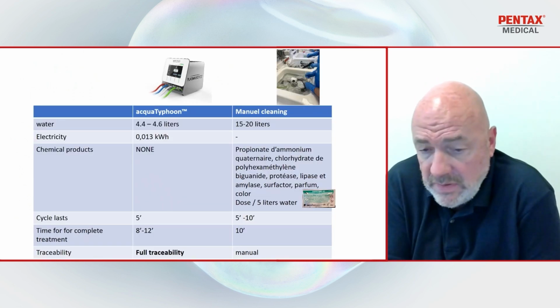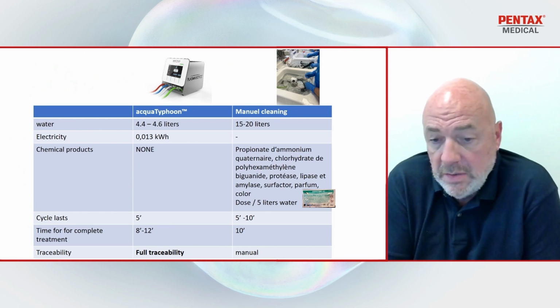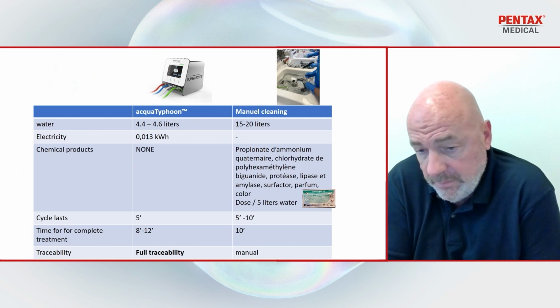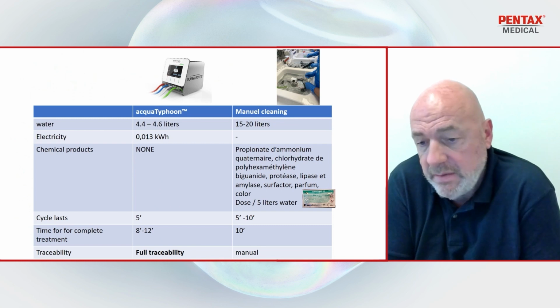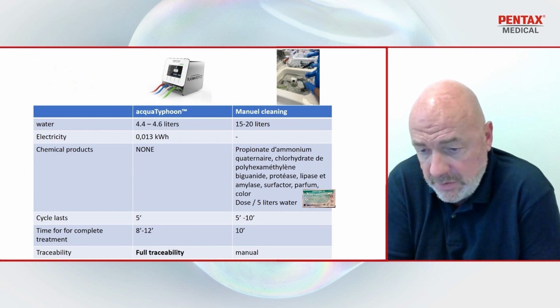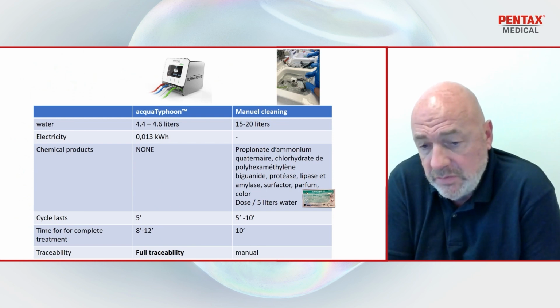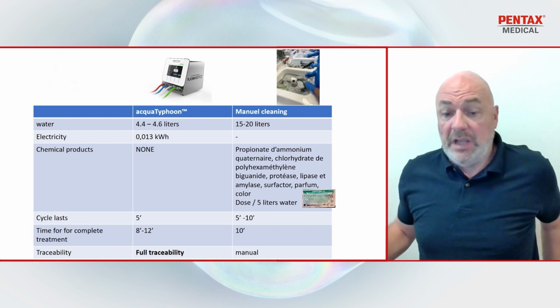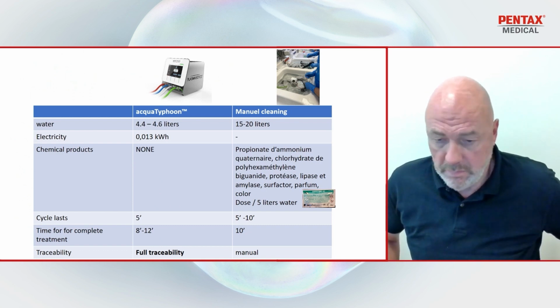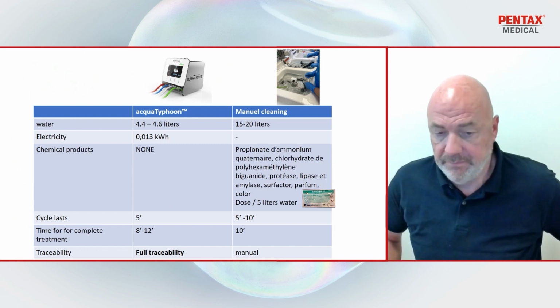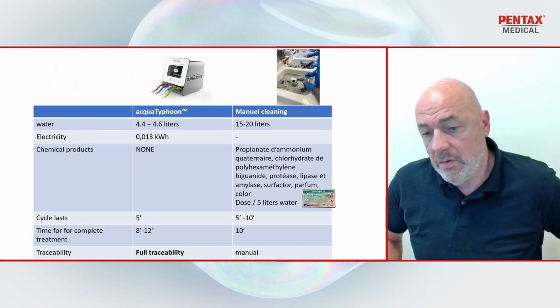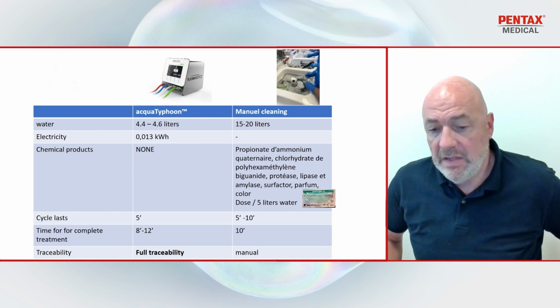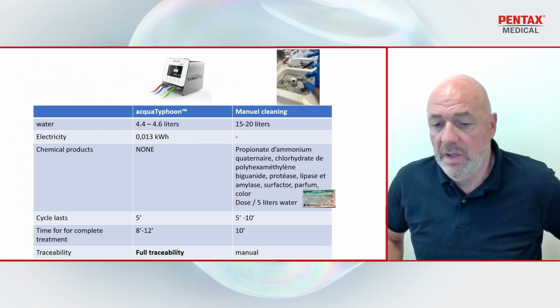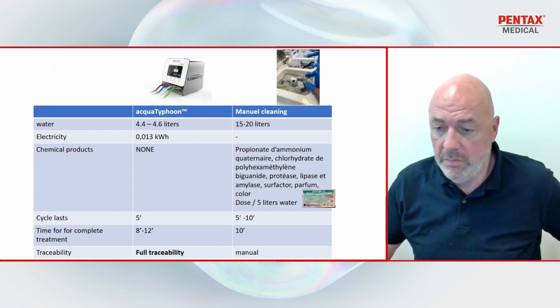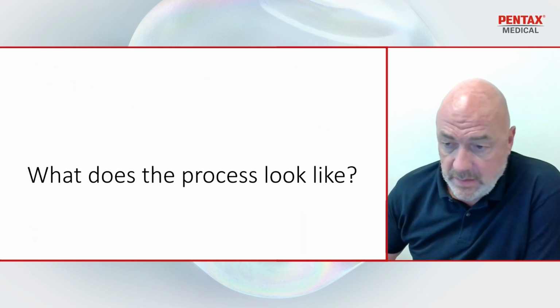So what is the difference between Aqua Typhoon and manual cleaning? The main difference is the water consumption: 5 liters for Aqua Typhoon and 15 liters for manual cleaning. The power consumption is very low. The chemical product for Aqua Typhoon is none, and for manual cleaning it is 1 dose for 5 liters. The duration of the whole cycle is quite the same. It's not a question. And the traceability is fully automatic with Aqua Typhoon. When you do the manual cleaning, you have to make a manual traceability.